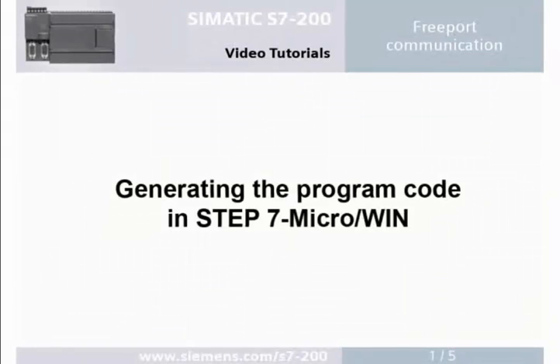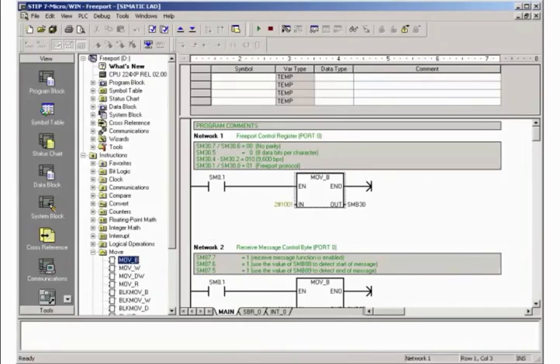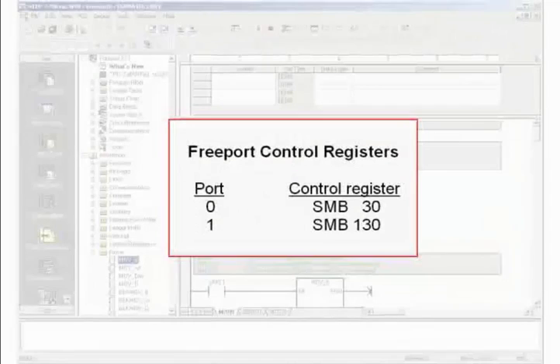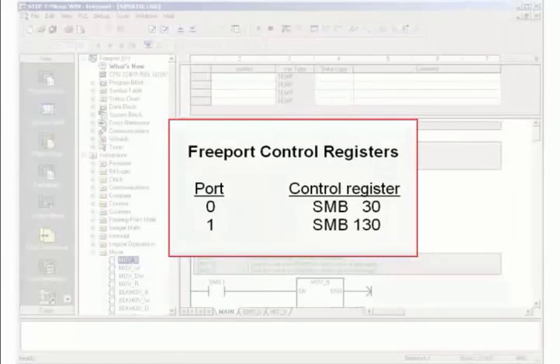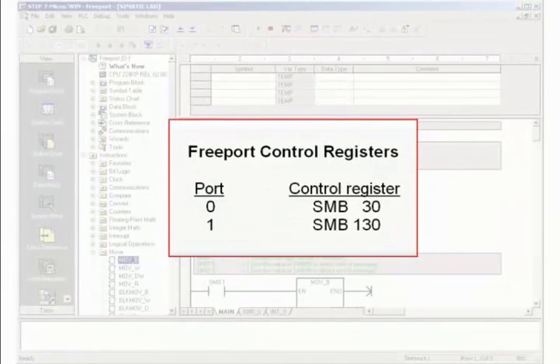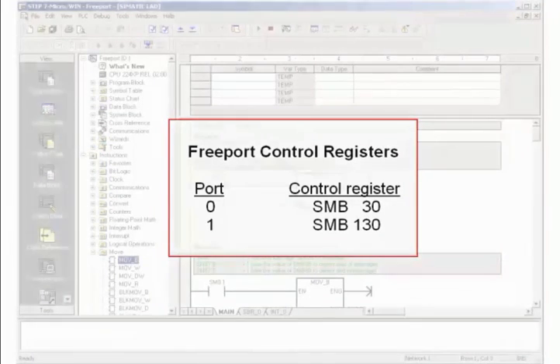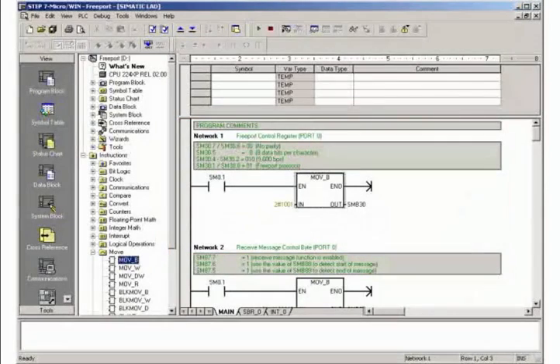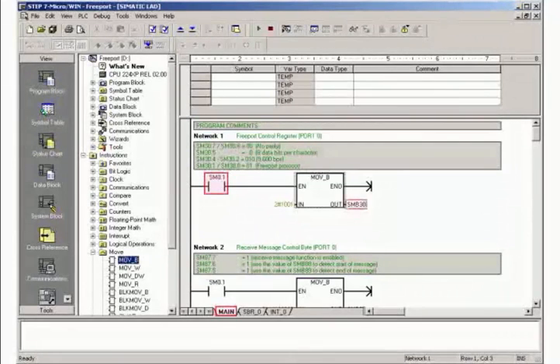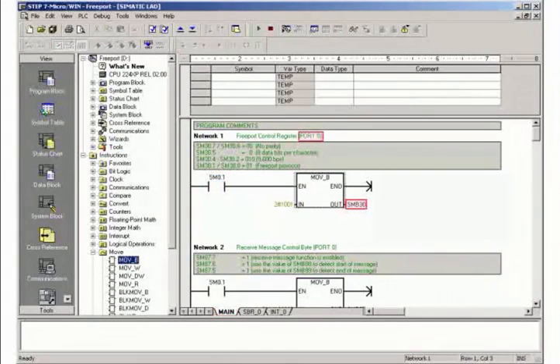Step 1: Generating the program code in STEP 7 MICROWIN. For the free port communication, the control register SMB30 or 130 must be initialized depending on the used communication port. In Network 1 of the operation block you initialize the control register SMB30 for port 0.